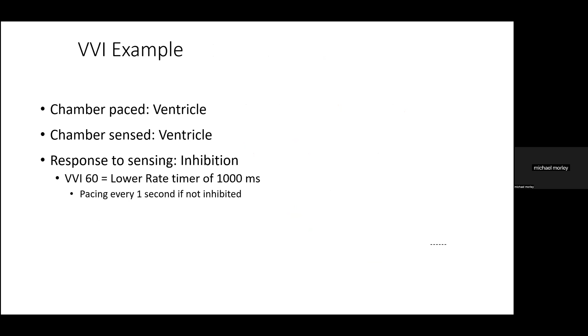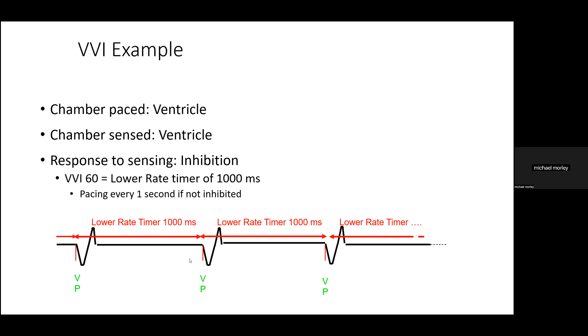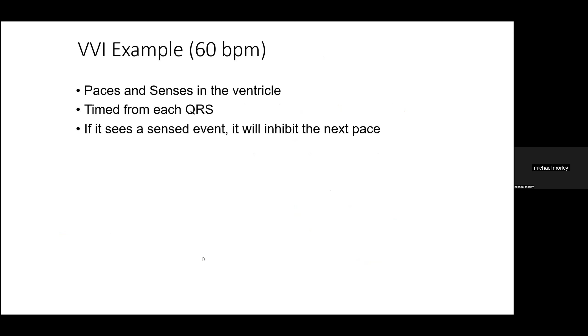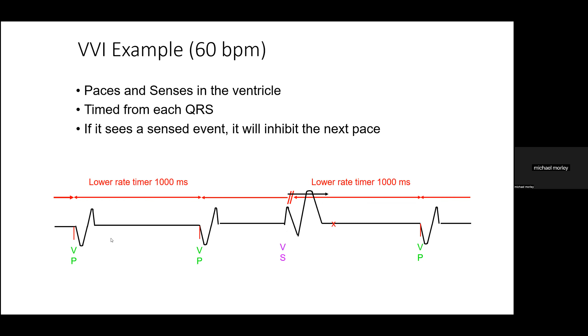So if we set our pacemaker at VVI 60, or 60 beats per minute, then what the pacemaker does is to pace. It waits a second and then it paces again. It waits a second and it paces again. However, if after it's paced and whilst it's waiting that second, it senses intrinsic activity, that inhibits the next pacing spike, which would have fallen at the cross. It restarts the stopwatch for the pacemaker. It starts its timer again, and then waits another second from the sensing of the intrinsic activity before it puts the next pacing spike in. And this is how demand pacing and how the timing works.